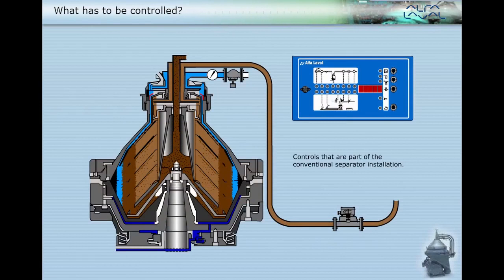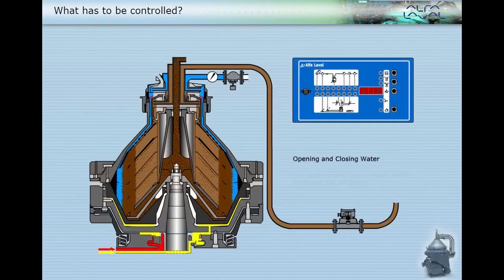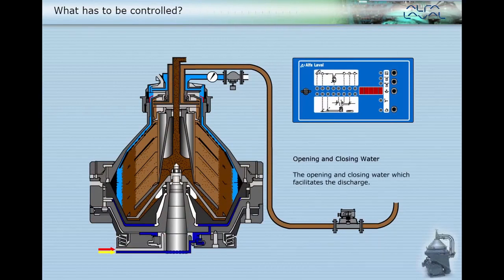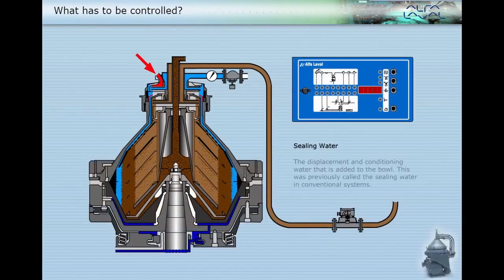Controls that are part of the conventional separator installation. The opening and closing water which facilitates the discharge. The displacement and conditioning water that is added to the bowl. This was previously called the sealing water in conventional systems.